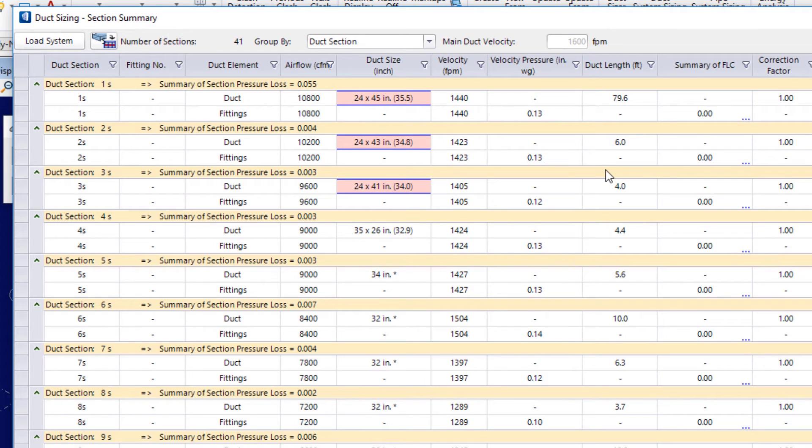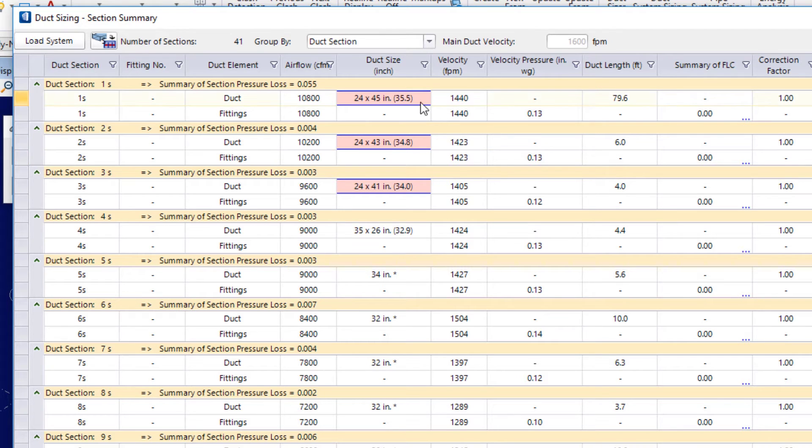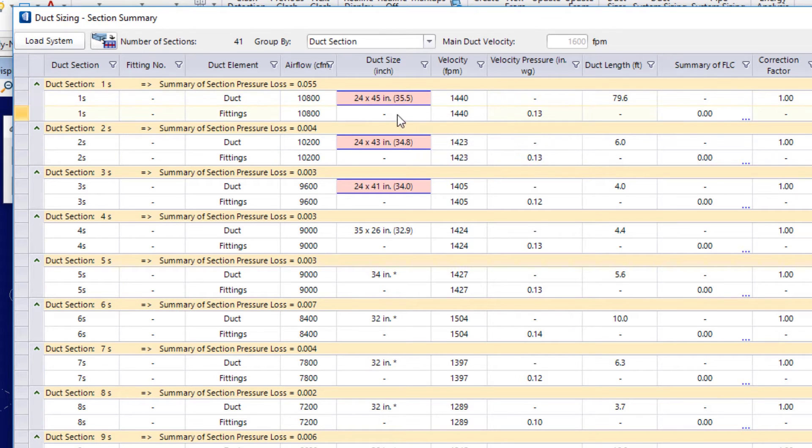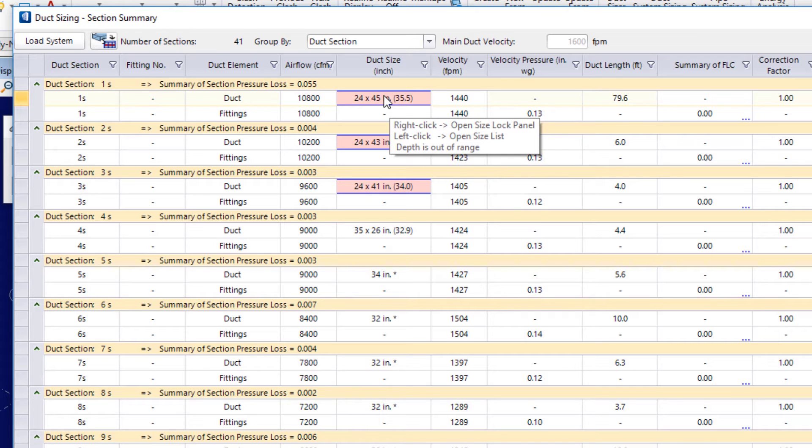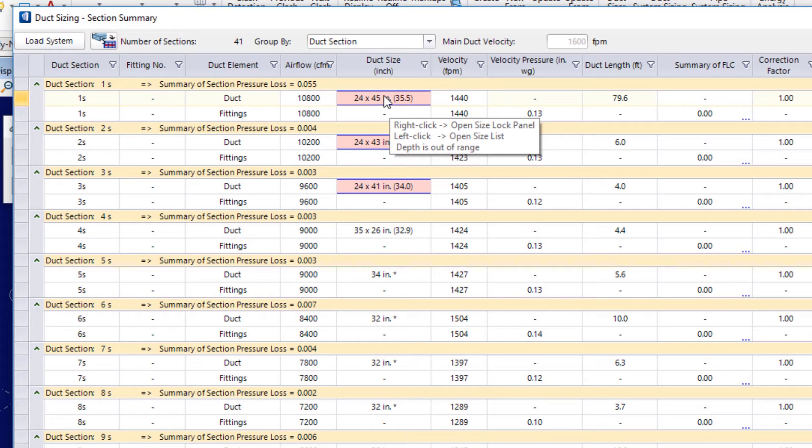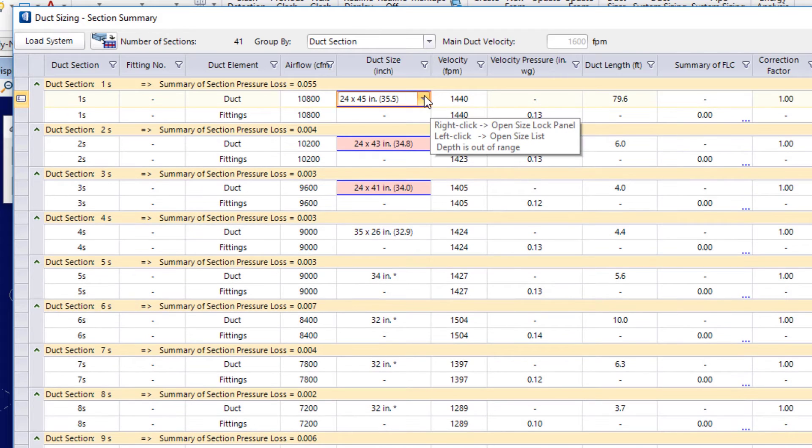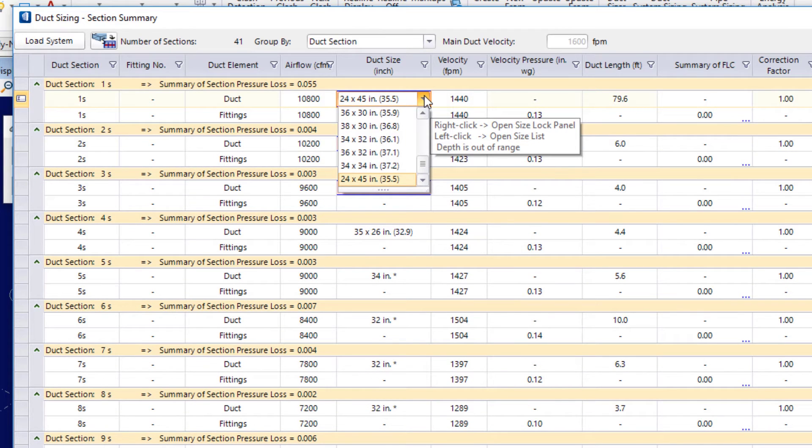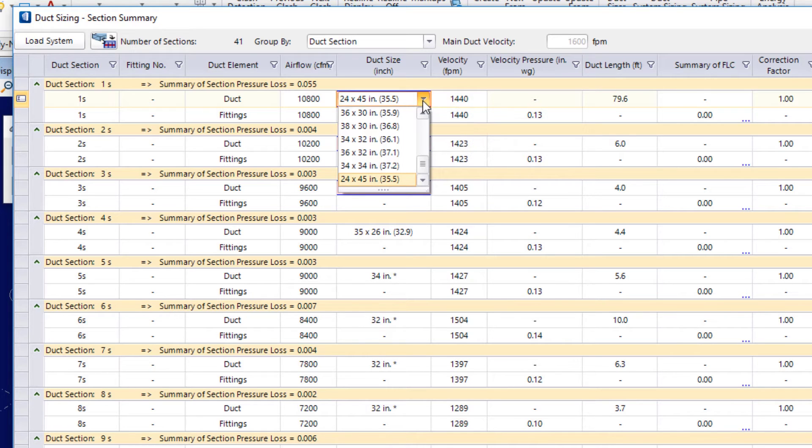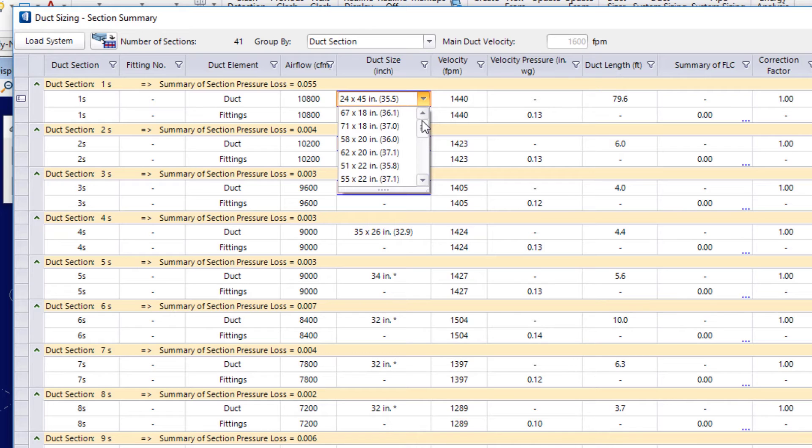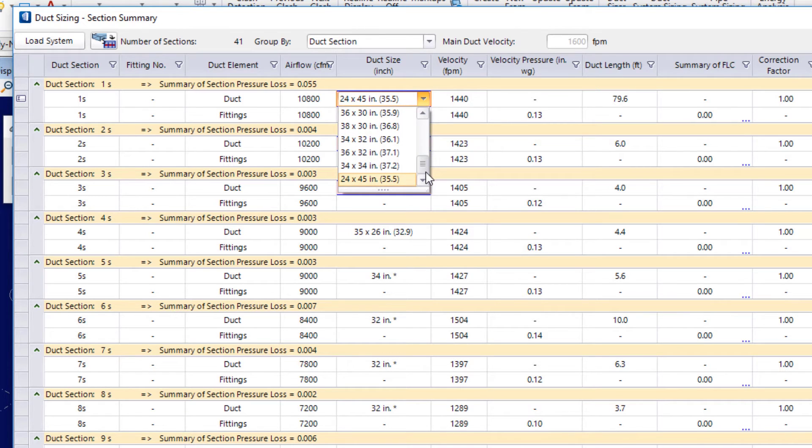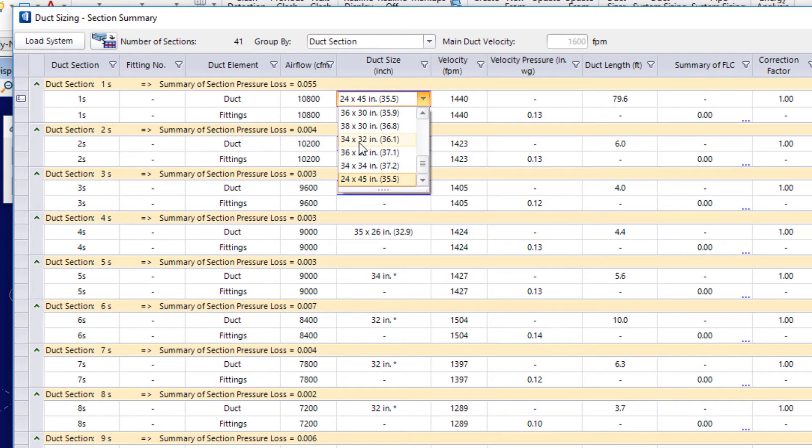So, now I see that my velocity is good. But, now I've got that red indicator in the duct size. And again, I can take a look at what it's letting me know. The depth is out of range. Now, I'll go ahead and select on this field. And I'll get a list of possible sizes according to my settings out there. So, I'll choose for example here. I'll choose the 34 by 32.